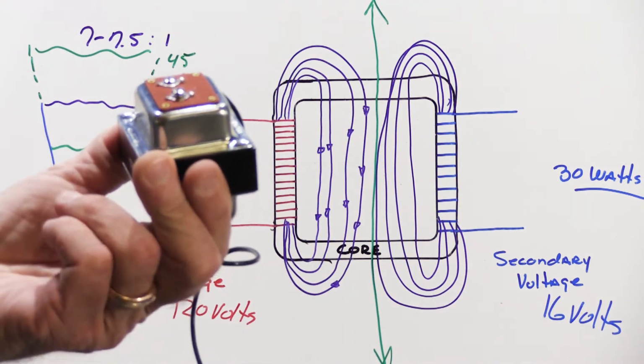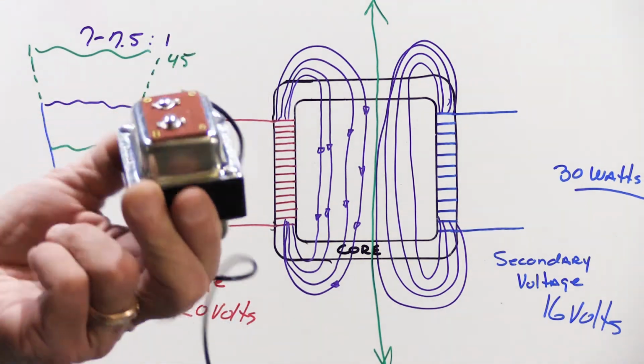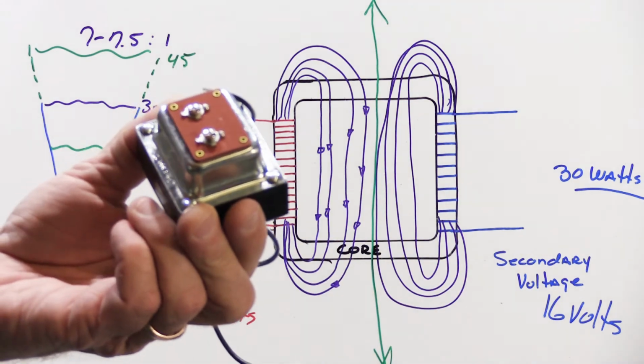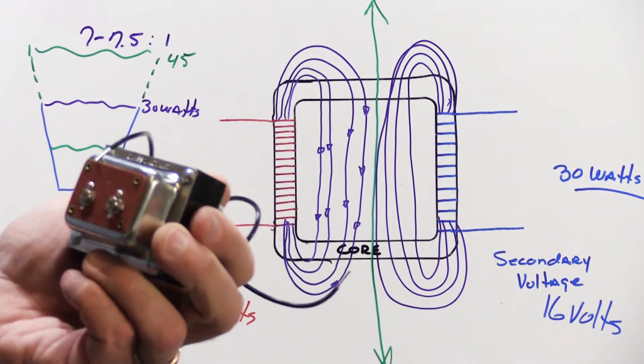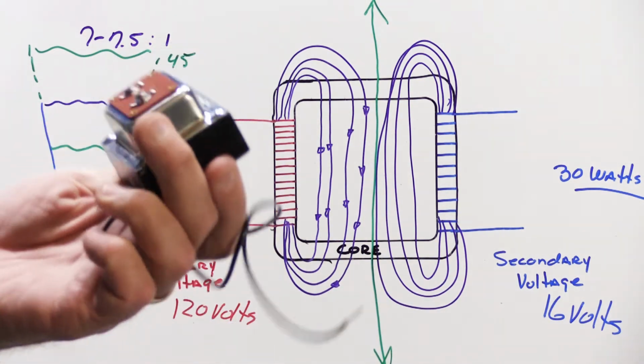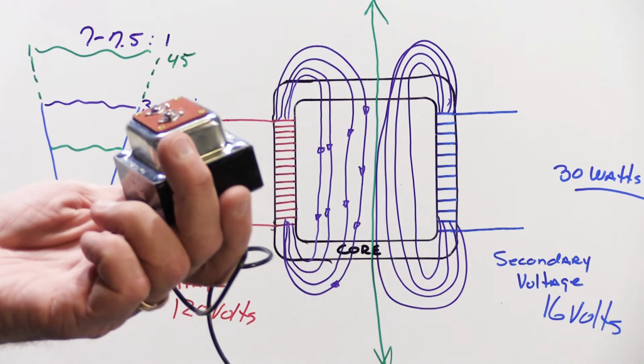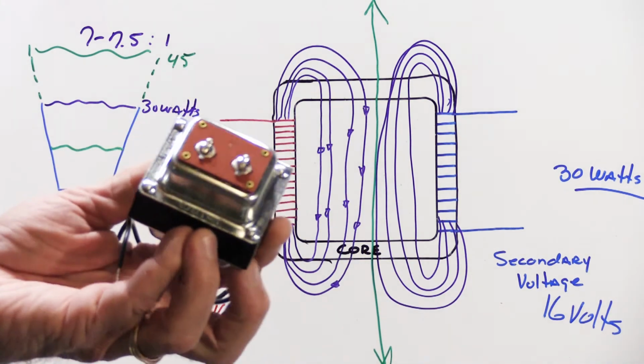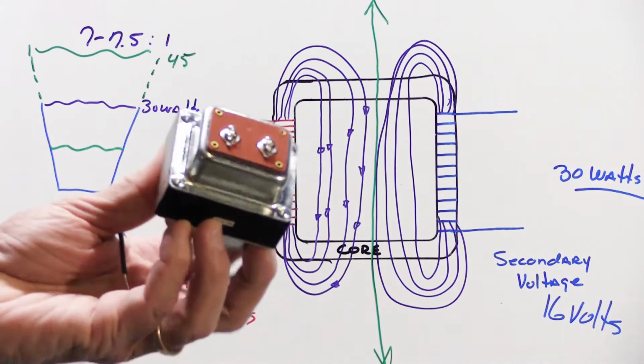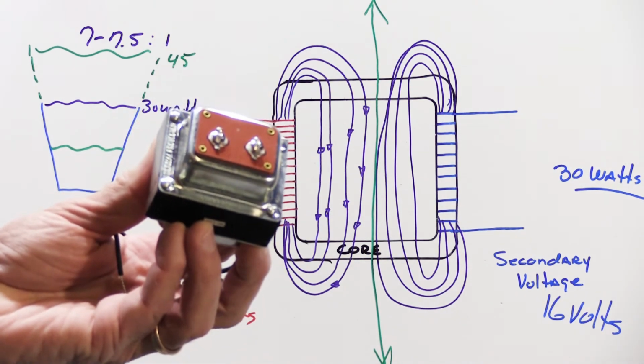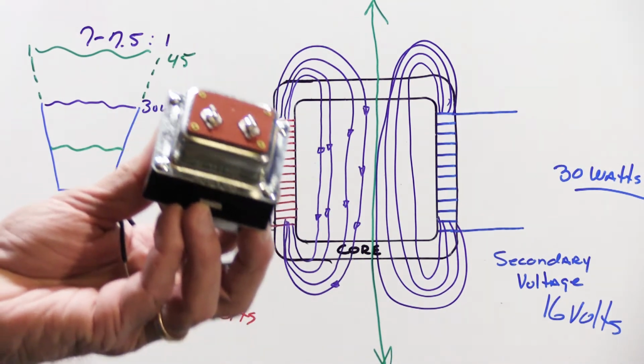I talk to a lot of people, and they'll call and tell me, well, I've had a problem with my NuTone Intercom system, and I checked the transformer and it's very hot, so it must be defective. And I say, no. Transformers are usually the casualty of a problem with the device that they're powering.